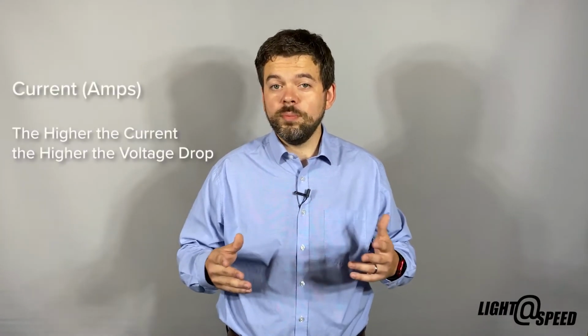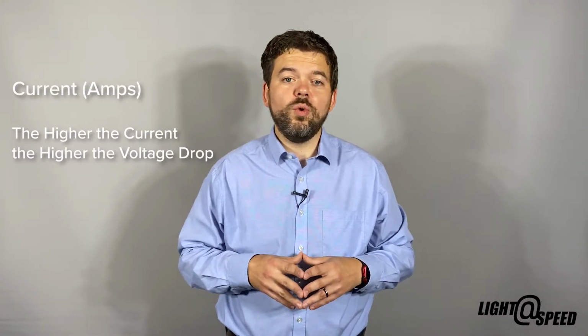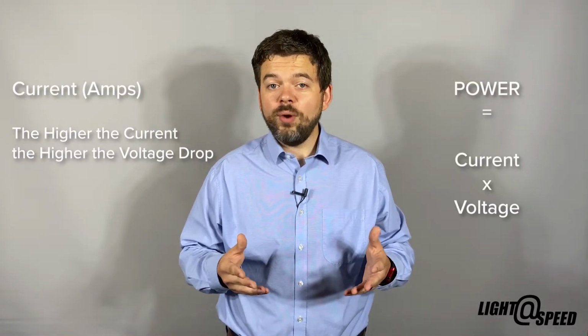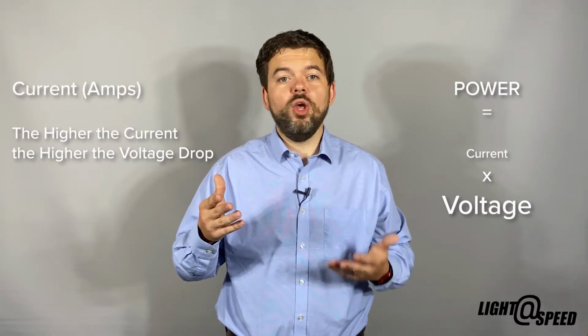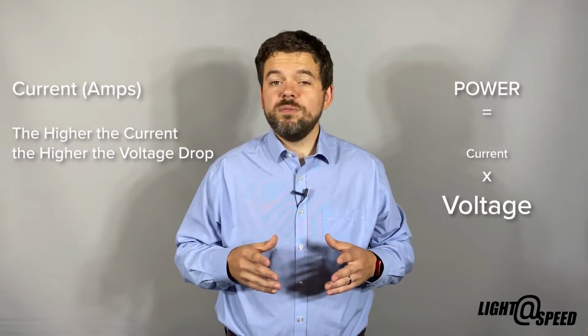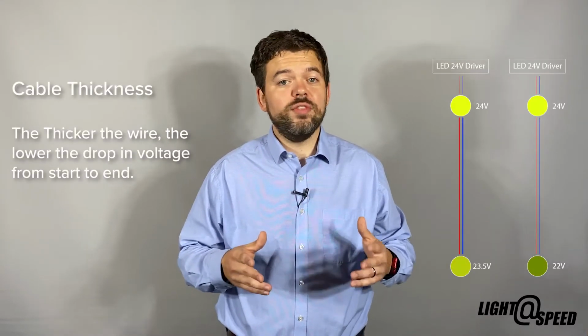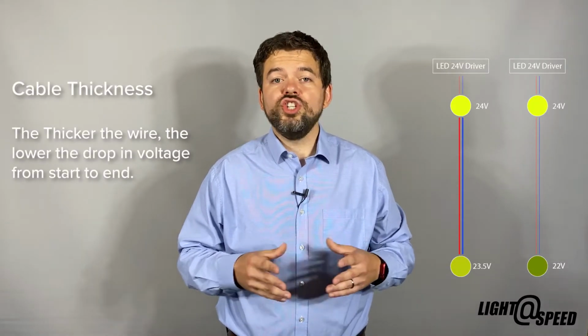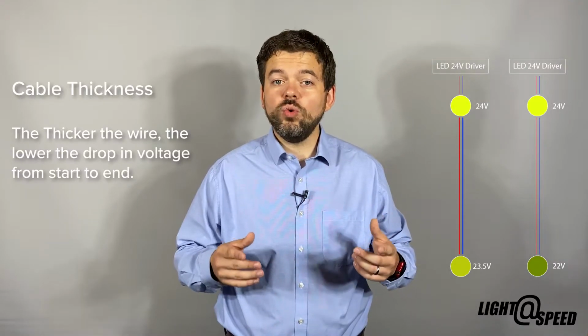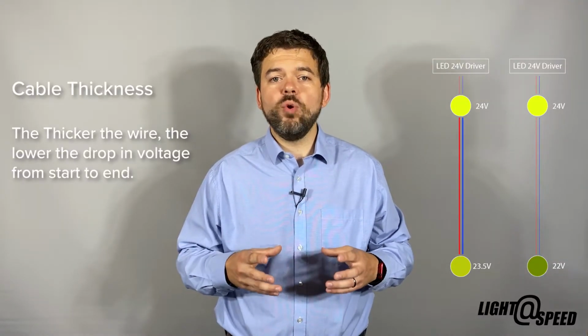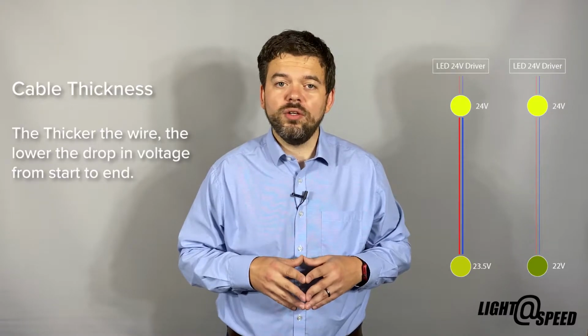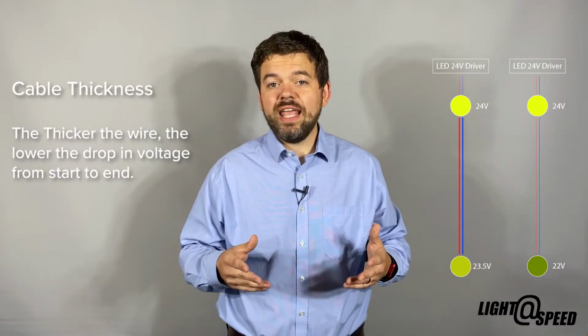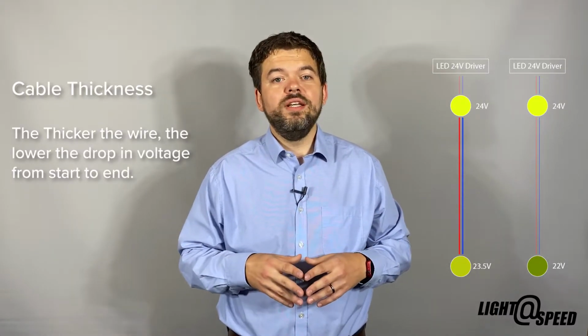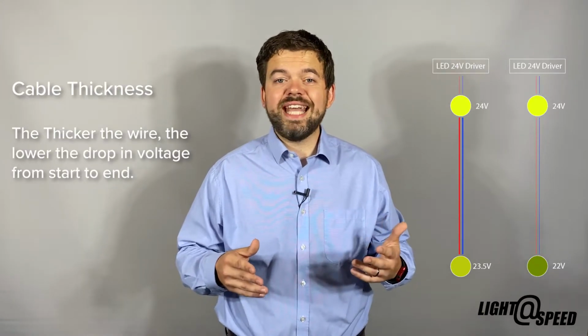Voltage drop is also proportional to the current running through the wire. For the same level of power, a higher voltage will have a lower current and would therefore experience less voltage drop. The same is also true for the diameter of the wire and its material. A larger diameter wire can handle more current and also has a lower resistance because there's more metal for the electrons to flow along.